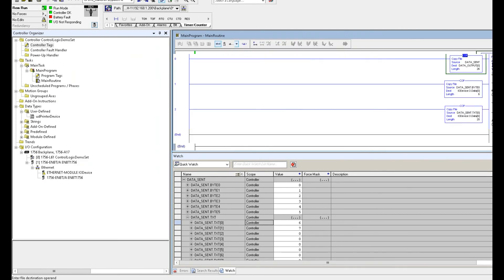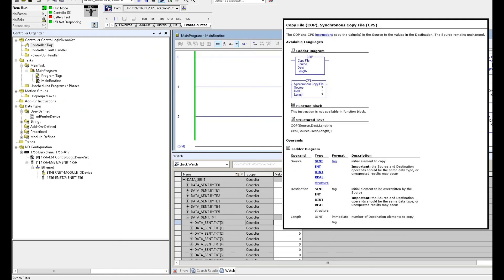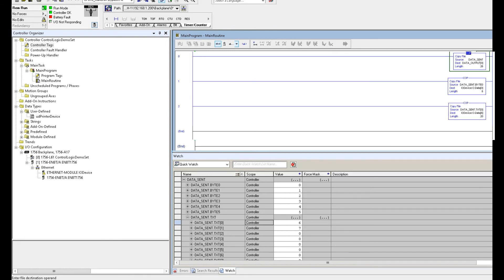To compare, the data_output buffer — I didn't change it — so if we watch this, it still has a gap there. So keep in mind, when we use COP, the source and destination structure must be the same. Otherwise it will cause unexpected problems. Especially when you go on-site, you think you can control the device following your mapping or drawings, but when you control the device, it is actually controlling other things. It will cause very dangerous issues.